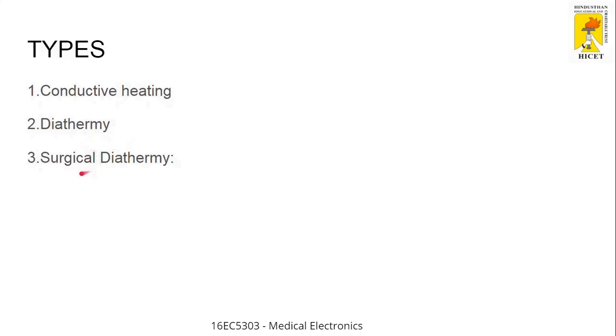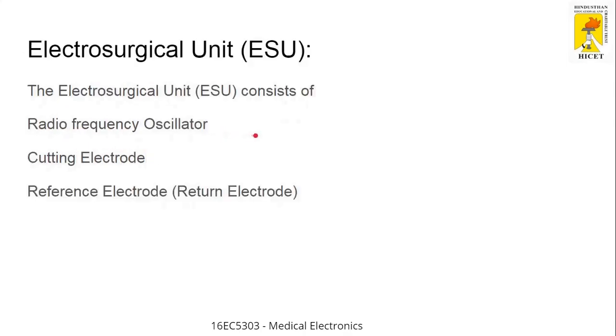Surgical diathermy involves a setup called the Electrosurgical Unit, or ESU. It contains radio frequency oscillators, cutting electrodes, and reference electrodes — these are the components used to build the electrosurgical unit. The key question is: how is the heat generated? The heat is generated using radio frequency oscillators.